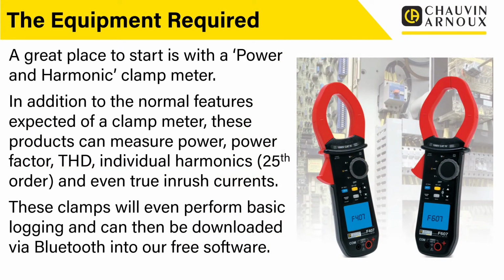A great place to start is with a power and harmonic clamp meter. In addition to the normal features expected of a clamp meter, these products can measure power, power factor, total harmonic distortion, individual harmonics up to the 25th order, and even true inrush currents. These clamps will even perform basic logging and can then be downloaded via Bluetooth into our free software - a very good place to start.